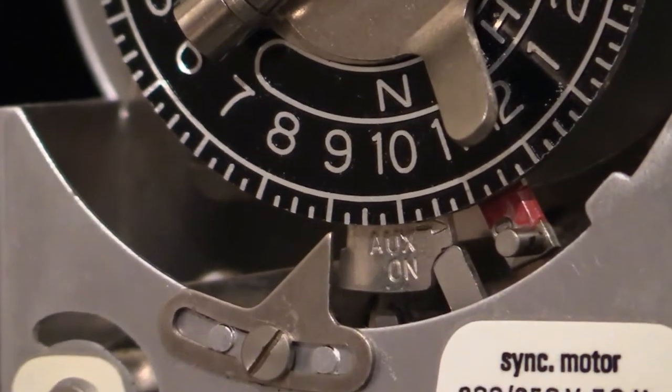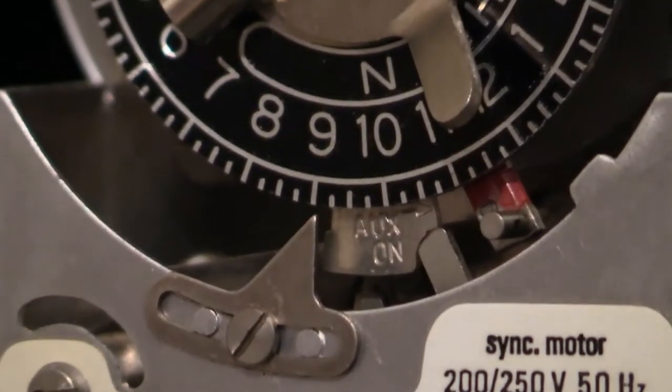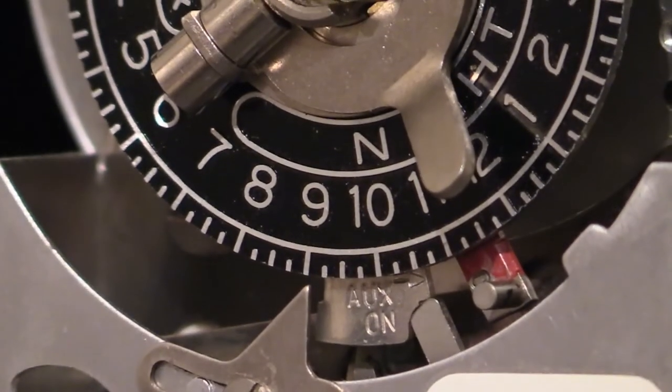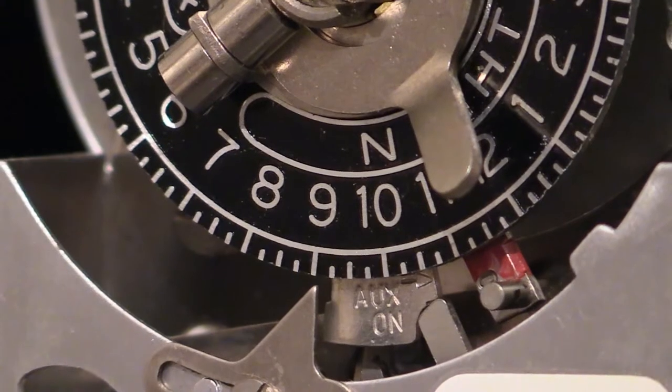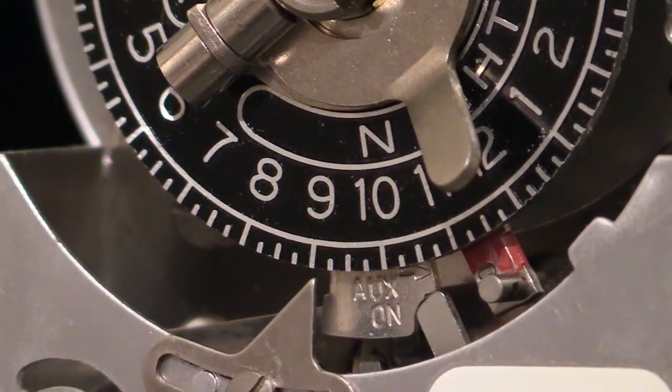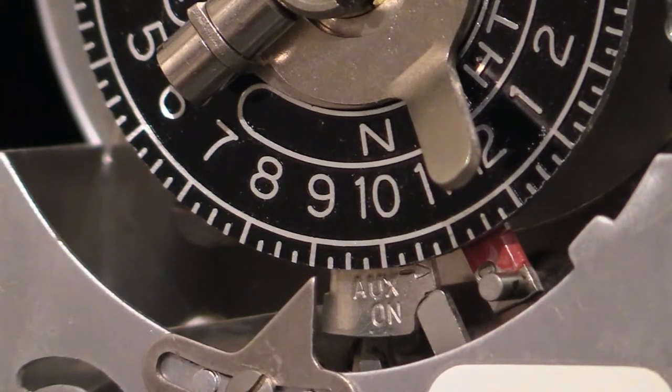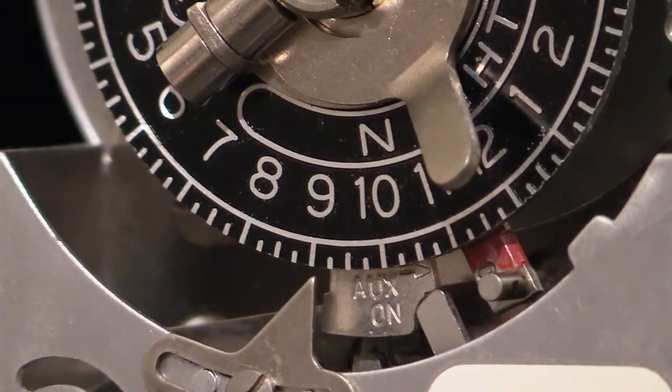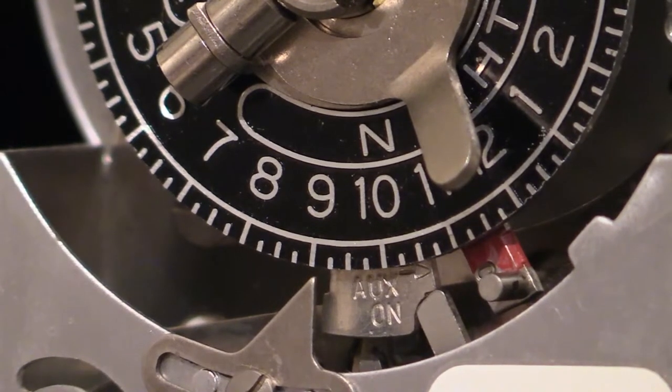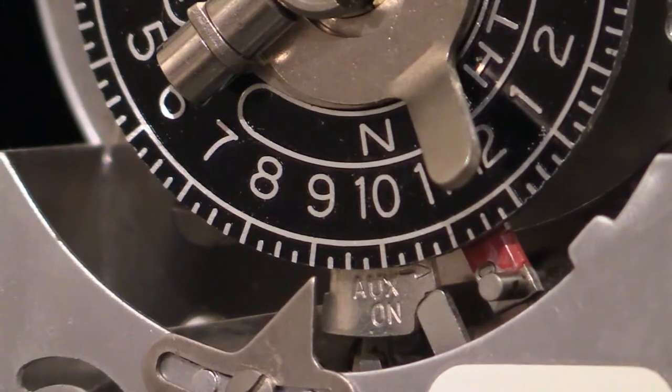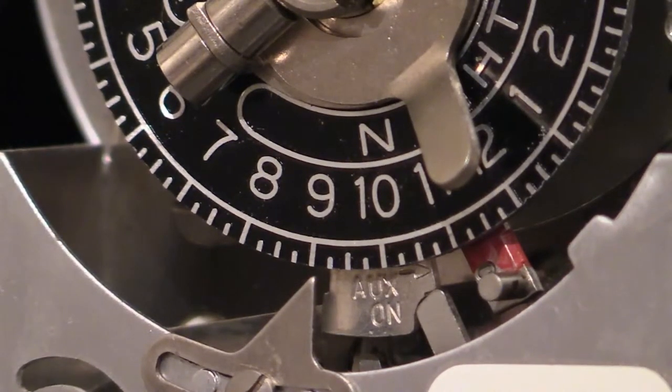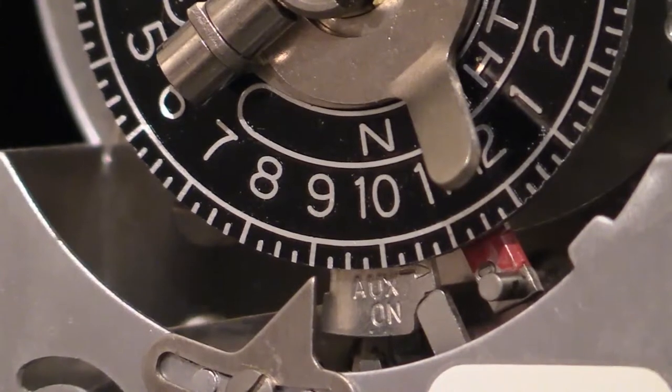You can also see that there is another little tag there and it says AUX ON written on it, and there's a little indent inside that. Now that AUX ON is in reference to that bridge which is up the top. When you set that AUX ON tab to a particular time on that clock face, that then determines when the bridge interacts with that little micro switch.